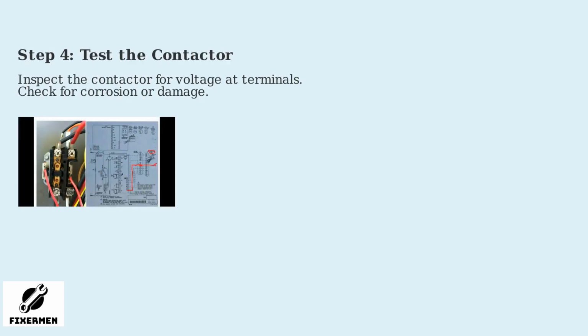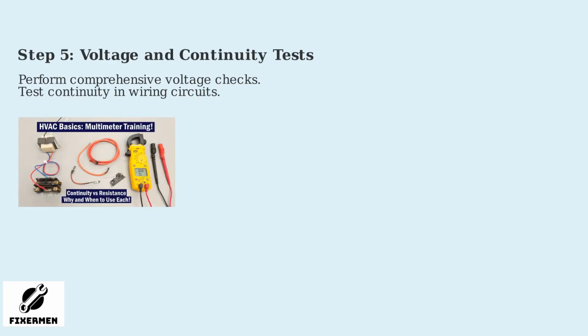Test the contactor by checking voltage across its terminals. Look for signs of corrosion or wear that could prevent proper electrical flow. Conduct thorough voltage and continuity tests throughout the system. Remember that 80% of startup problems are electrical in nature. For suspected refrigerant leaks or compressor problems, always consult a professional. These require specialized tools and certification.